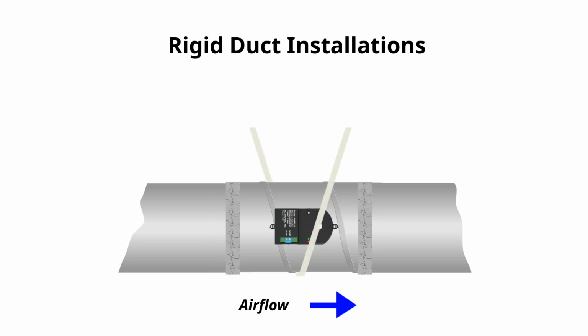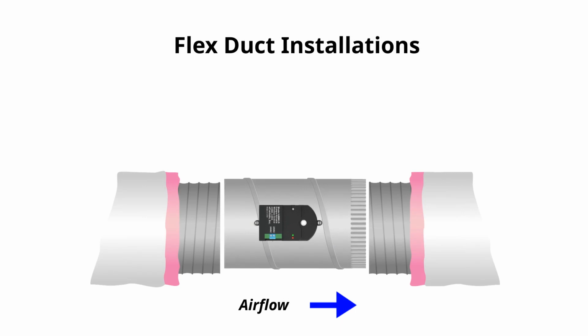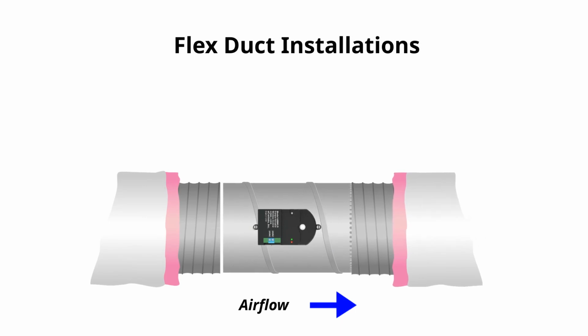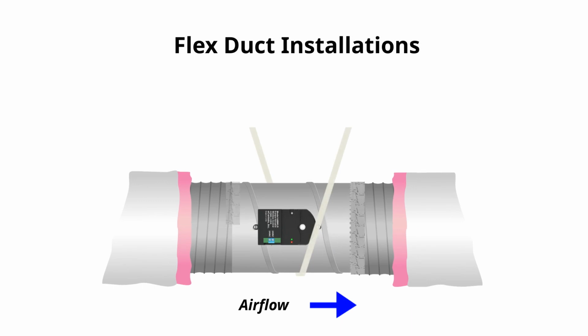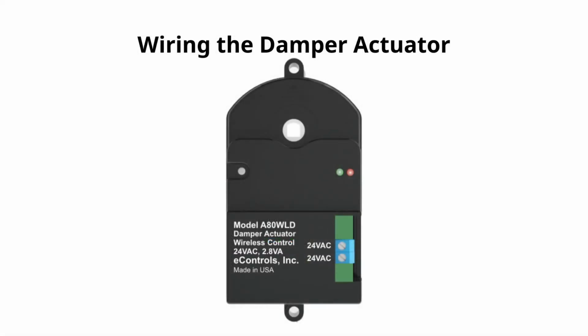For installation in flex duct, pull the flex duct over each side, making sure the crimped end is in the direction of airflow. Again, support the damper if needed, and tape to properly seal. If multiple dampers are required for your installation, continue installing the dampers. Now let's wire the damper actuator.